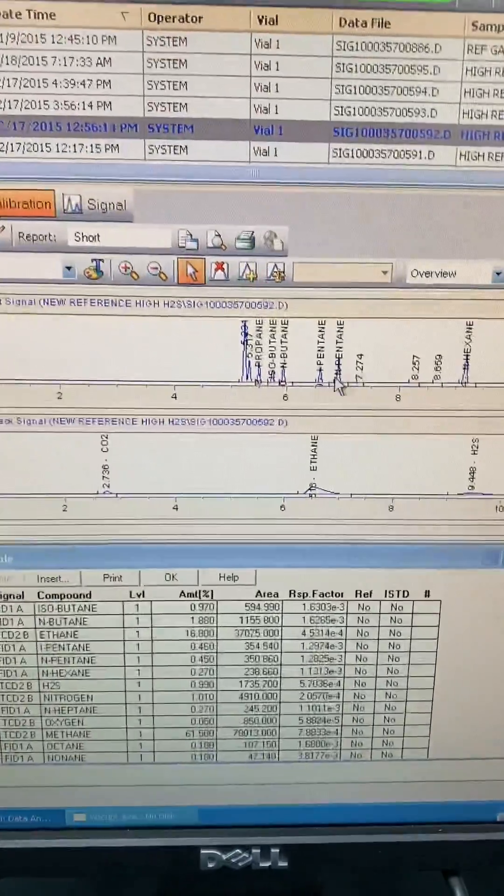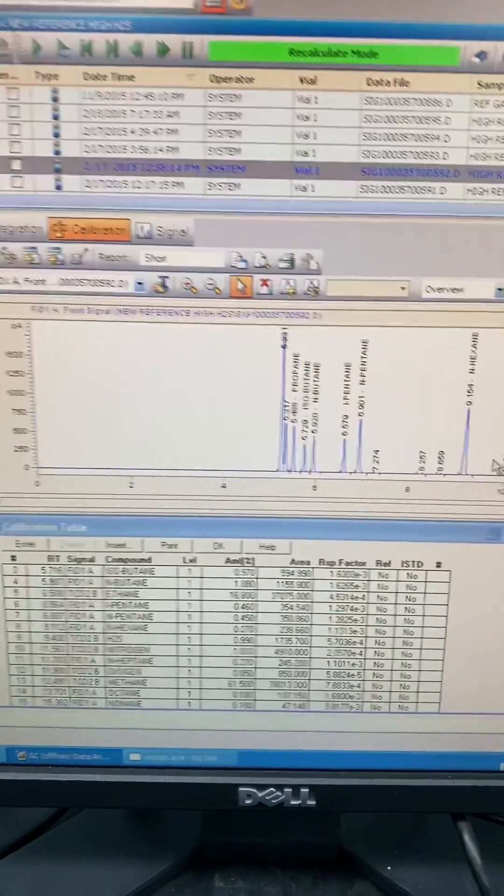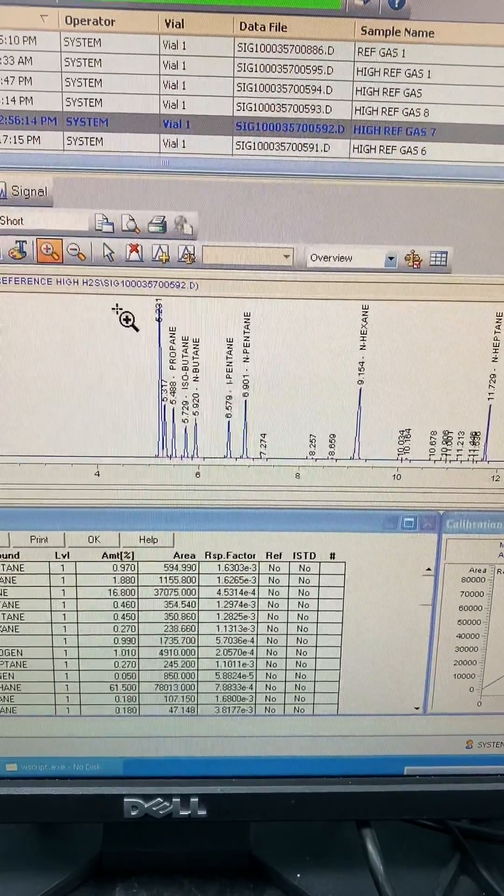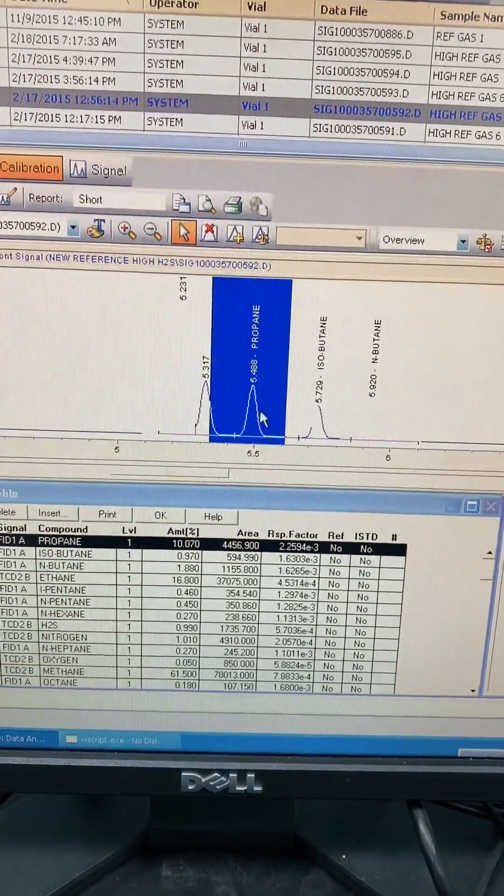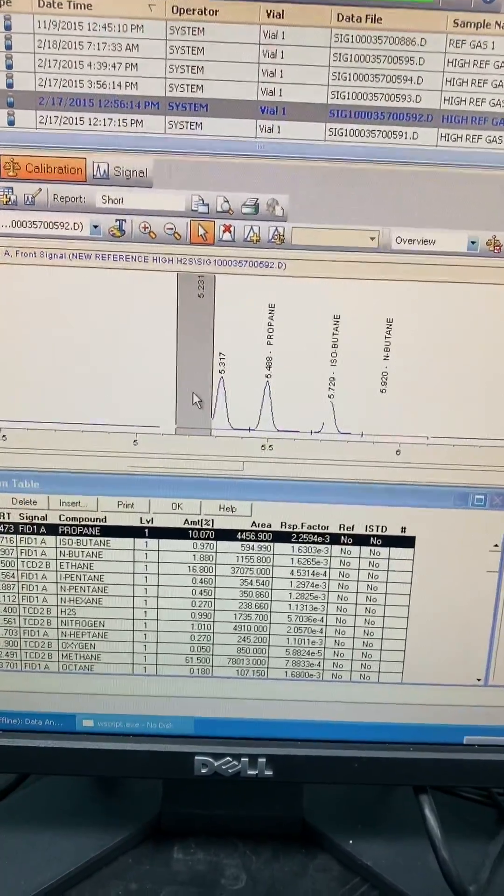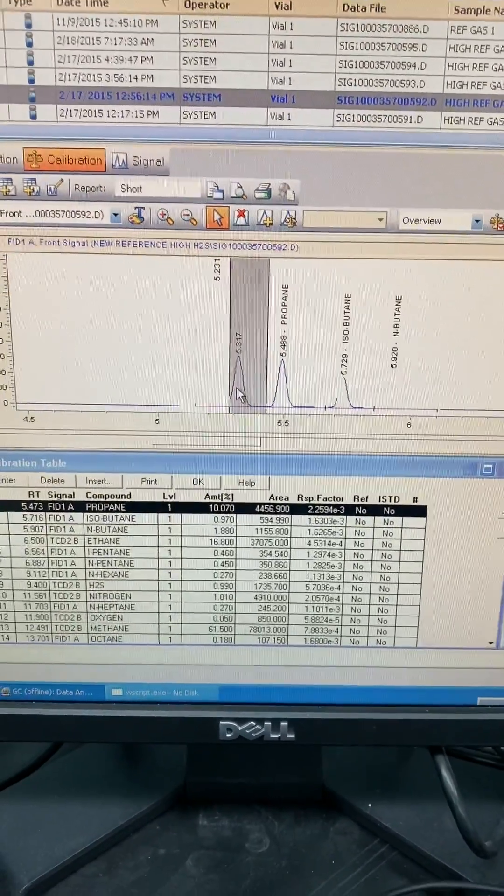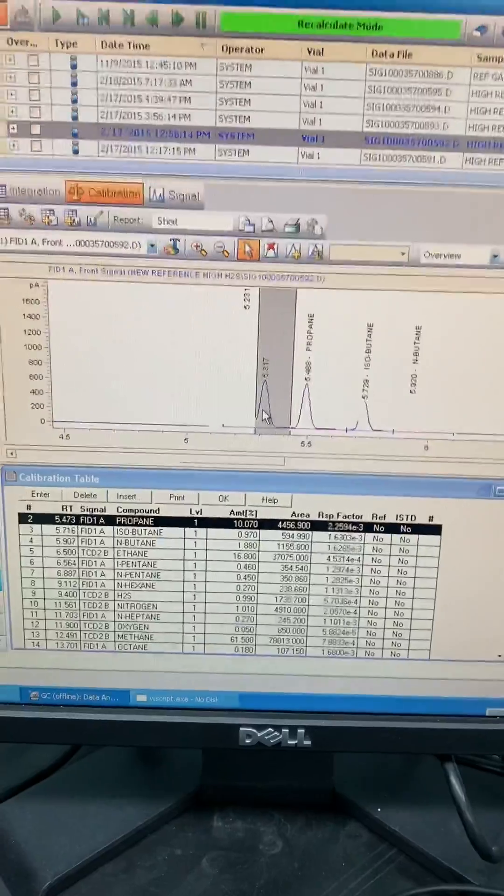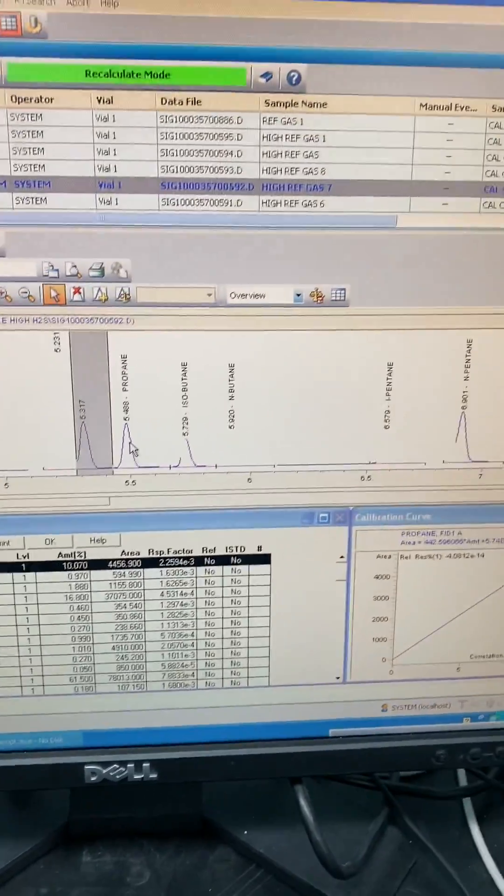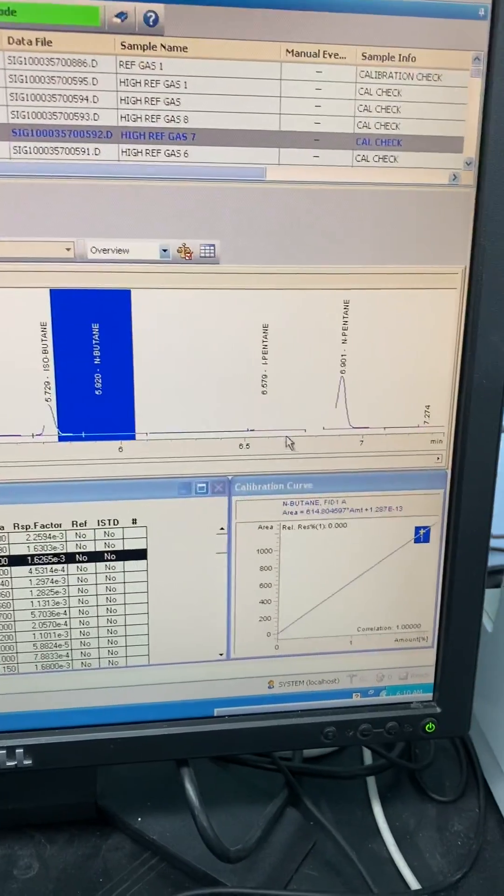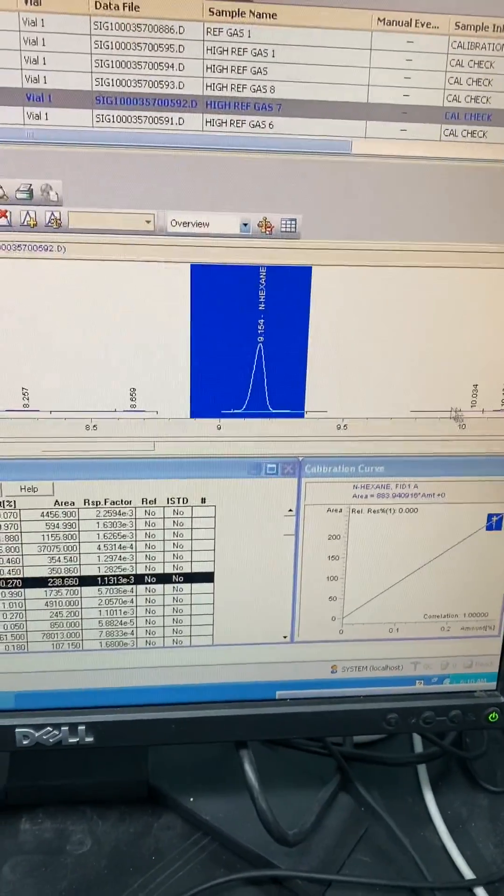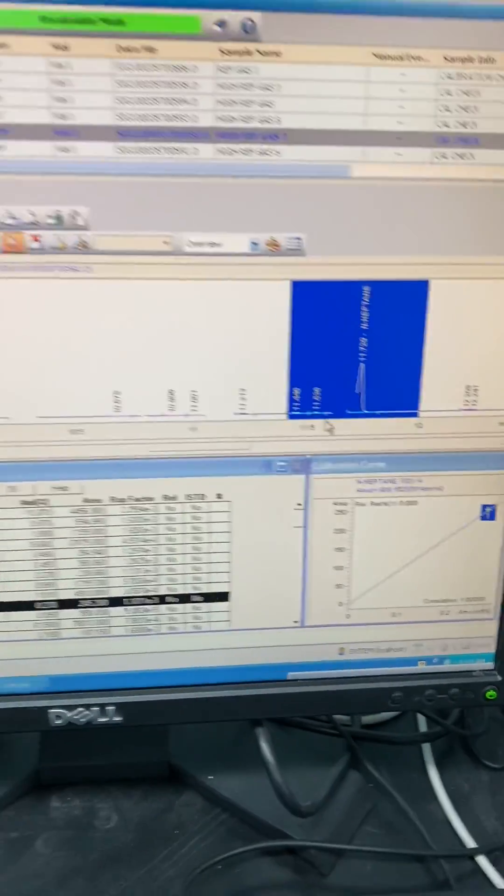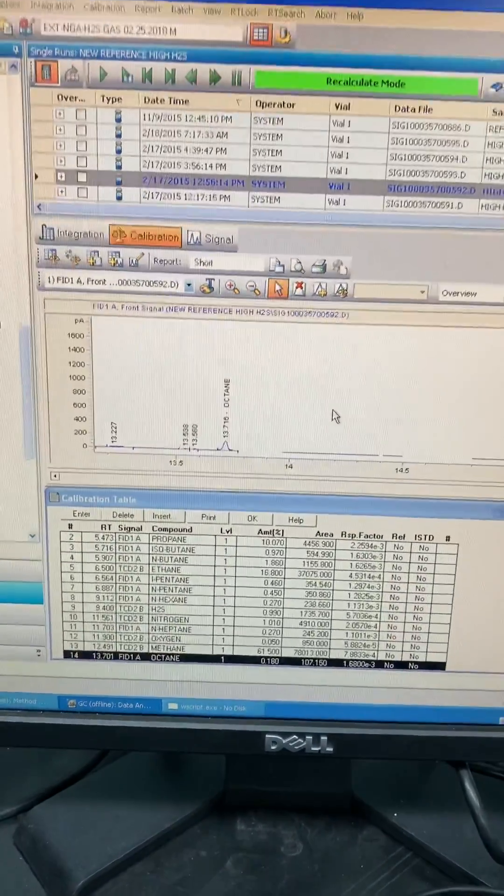Let's go to the FID. To make it easy for you, you can select only FID from here. And you can see all the peaks here. The first two peaks, I have here the propane, the first peak identified in the FID. Why I don't have those peaks named or identified? They are already eluted and detected. However, this is the methane and ethane. But in my method, I prefer to take the quantification for methane and ethane from TCD detector because it's high sensitive for low molecular weight. So propane already identified. Isobutane identified. Normal butane identified. Iso and normal pentane identified. Normal hexane. Normal heptane. Iso and octane. So that means all my peaks now are identified.